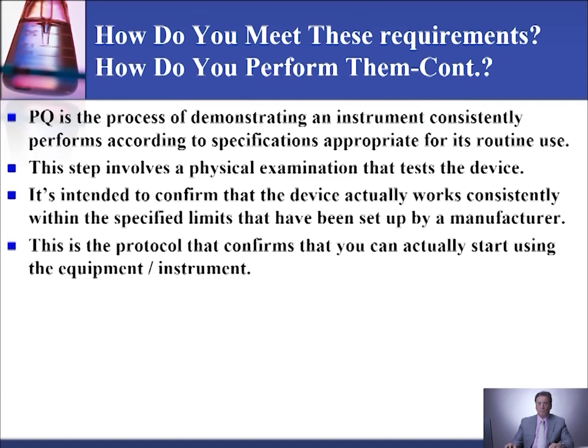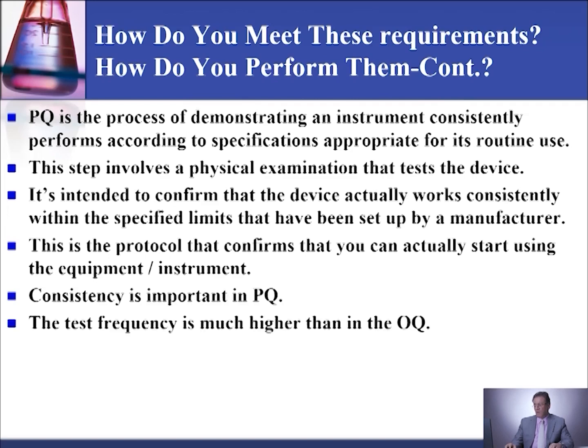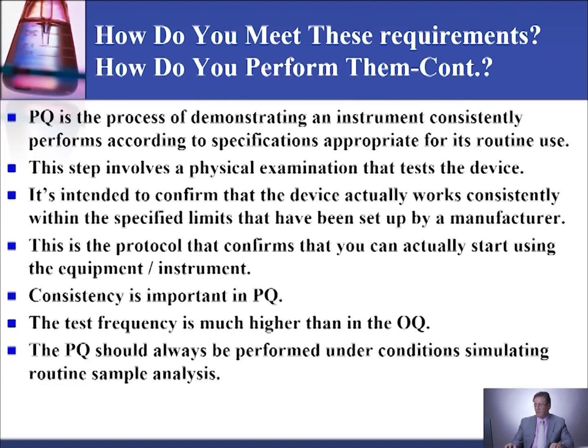So this is the step where, when you are done with it, you will be able to use the instrument for patient testing. Consistency is important in performance qualification. The test frequency is much higher than in the operation qualification. The PQ should always be performed under conditions simulating routine sample analysis.